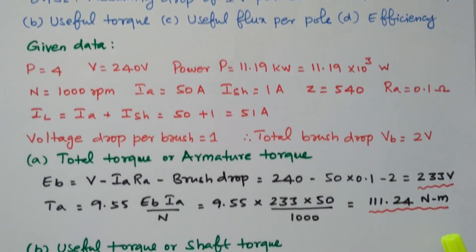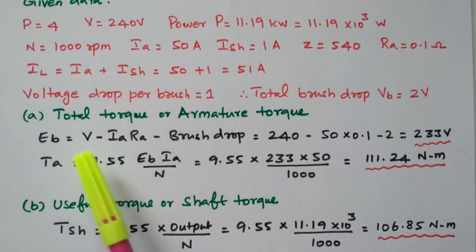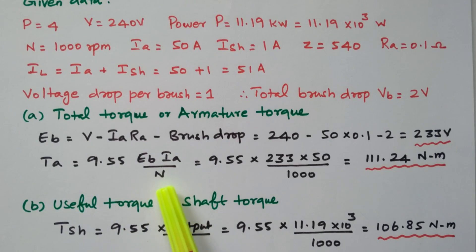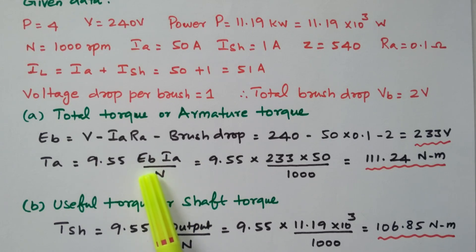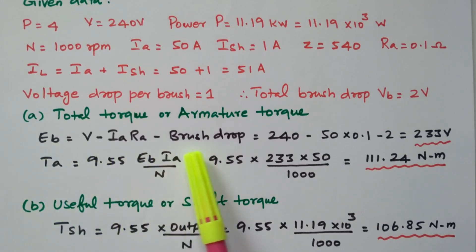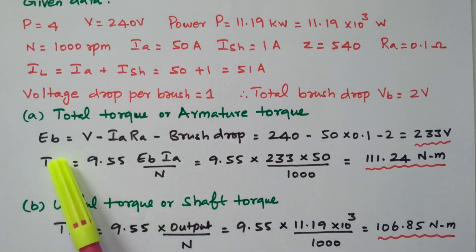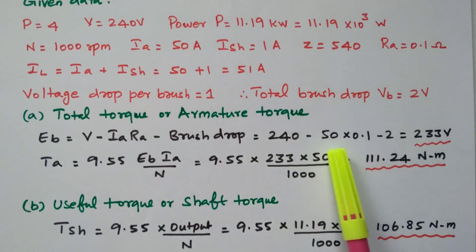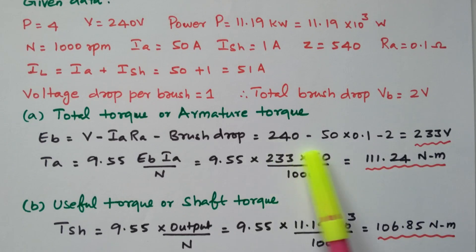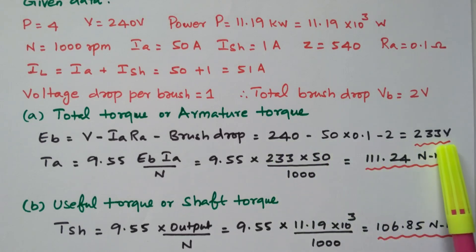Now we find the total torque, also called armature torque — the torque developed in the armature. The formula is TA = 9.55 × EB × IA / N. IA and N are known, but EB must be found first. Back EMF: EB = V − IA·RA − brush drop = 240 − (50 × 0.1) − 2 = 233 V.